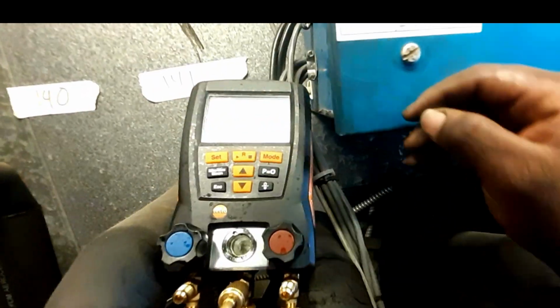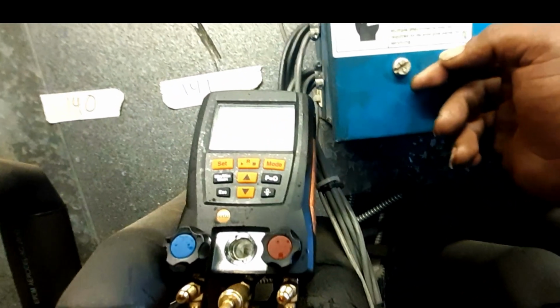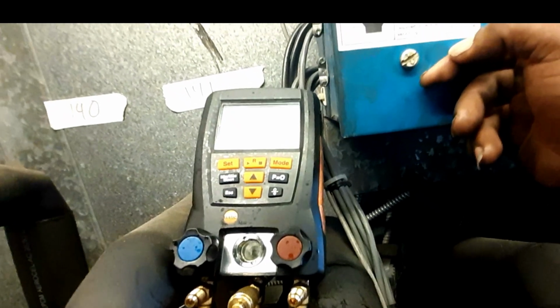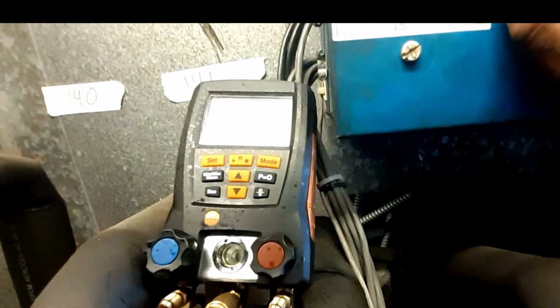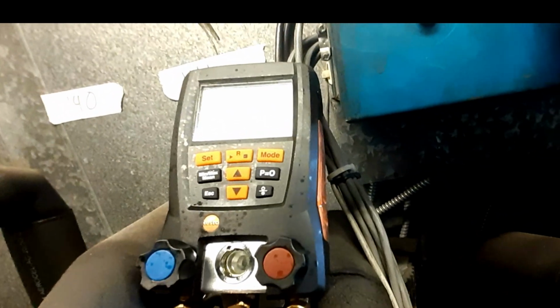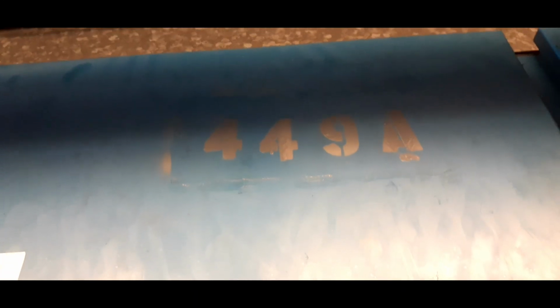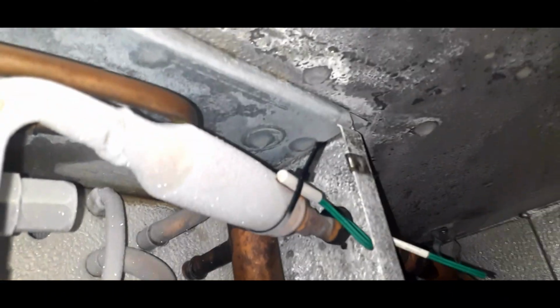So let's just go ahead and check this out. So far we had 11 and 10 PSI. So that is 100% open, even though it's off by a few points. What refrigerant is this? R449A. We're gonna need to know that when we go down and check our superheat. So, where is my TXV? Right back there, look at that. Iced up, like it's kind of starving.